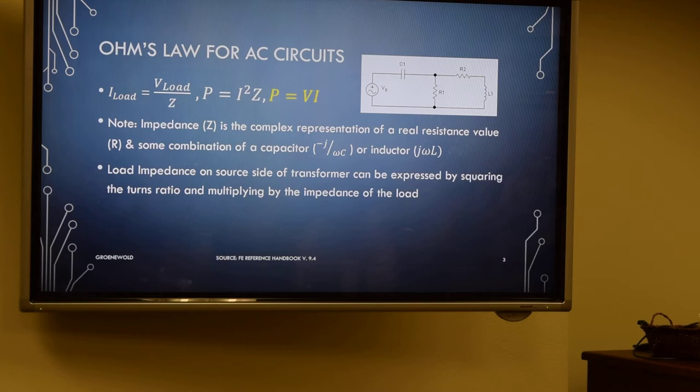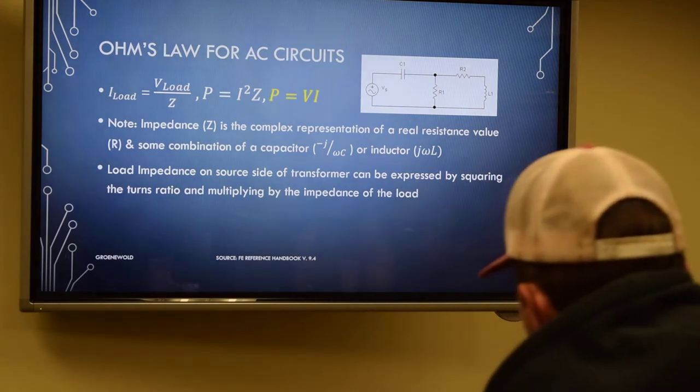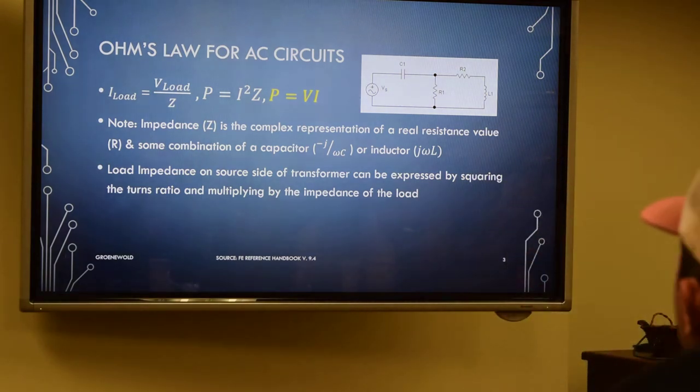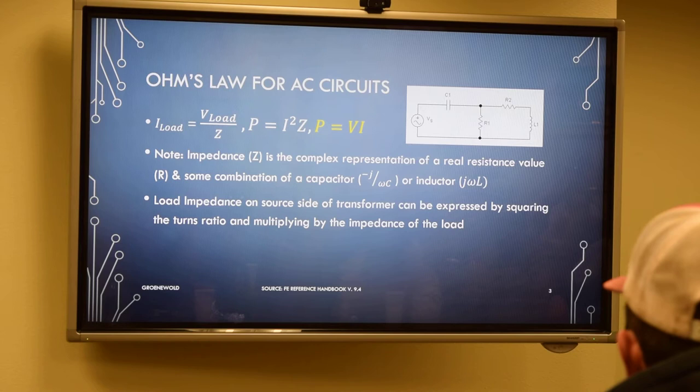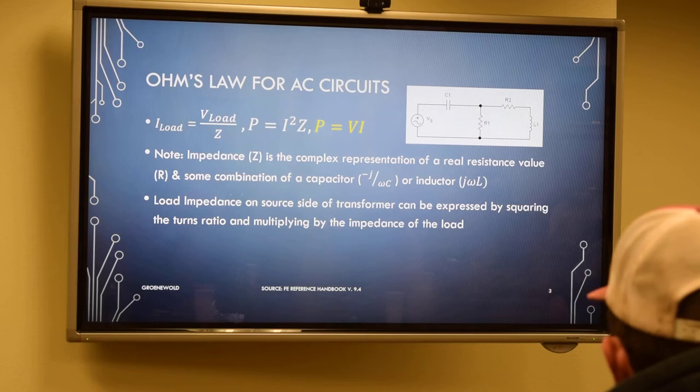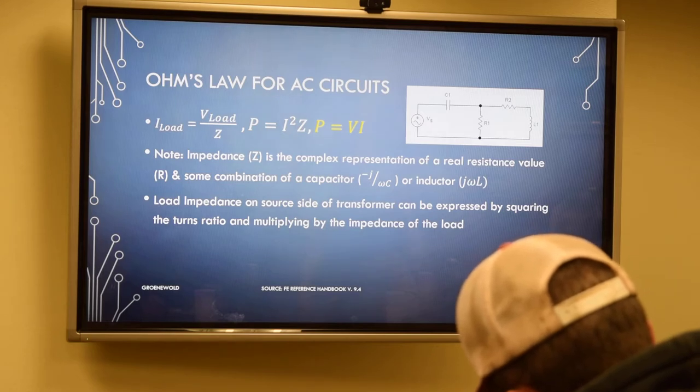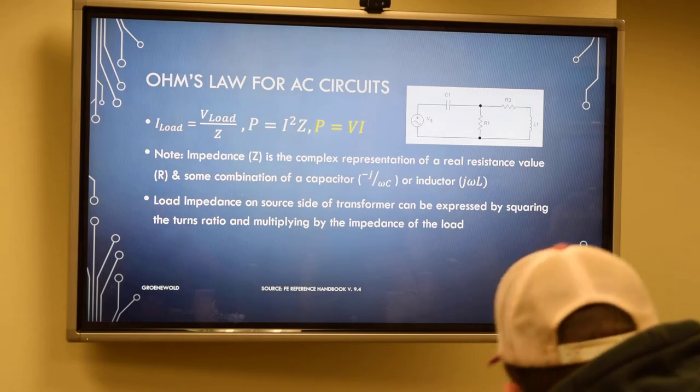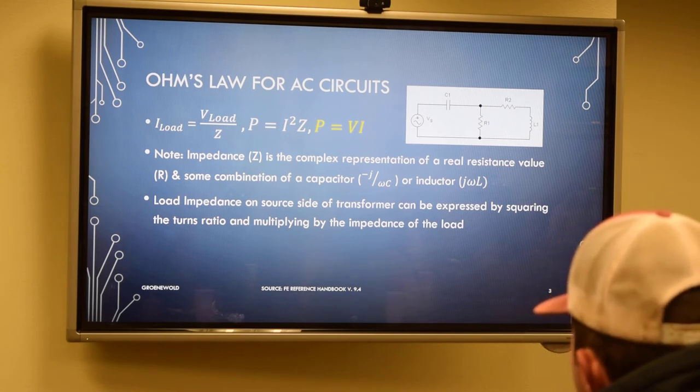Impedance is the complex representation of a real resistance value, which would be your R1 and your R2, and some combination of the capacitor, which is the C1, or some form of inductor. Each power line will have its known resistance and impedance value. When you're trying to calculate any load impedance, a load impedance on the source side of a transformer can be expressed by just squaring your turns ratio and multiplying by the impedance of the load side.